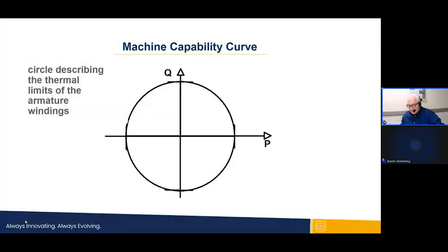The thermal limits of the output of the generator or of the inputs to the motor are described on the real power and imaginary power plane, the PQ plane as you see here, as a circle, the radius of which is the machine's apparent power limit. This circle defines the first component of the capability curve. Next slide.